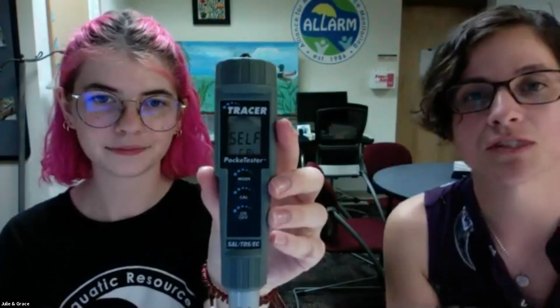And one of the things that you'll notice in our meter is on your meters, you have a little L and an M circled, denoting that you have a saved calibration, and we just wiped ours clean. The other thing that will happen is it will go to salinity mode. So you do need to make sure you're in conductivity mode. For those of you who are like, I'm not going to remember that one, page 20 is there. And we also cover the reset process in full details in our conductivity meter video. So, all right. With that, but you don't need to reset right now. We can practice resetting at the end so that you have your saved calibrations.